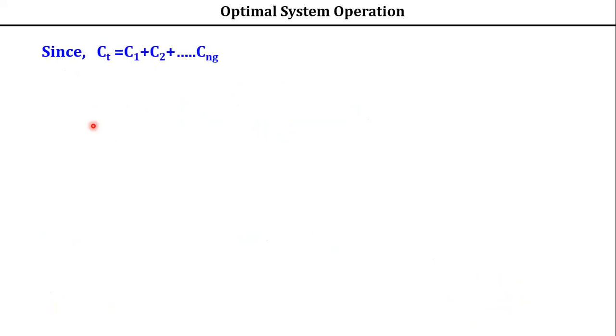Now, since Ct is equal to the sum of all the individual costs of generation, Ct is equal to C1 plus C2, etc. plus Cng, isn't it? So therefore, how to get dou Ct by dou Pi, where this is the total cost? You are going to get dCi by dPi, where i is varied from 1 to Ng. Understood? So because of this, dou Ct by dou Pi is equal to dCi by dPi, in turn equal to lambda. Only this term we are getting, etc. Because we know that total cost is the sum of individual costs, this can also be written as dCi by dPi. Understood? So it is equal to lambda.